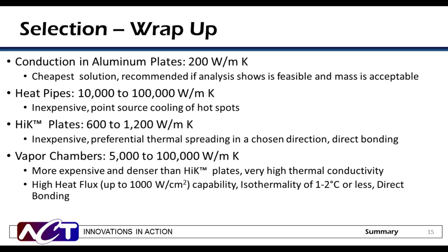Here is a summary of selection criteria across each technology. Aluminum plates have a thermal conductivity of 200 watts per meter K, move heat in two dimensions, and are usually the cheapest solution — use them whenever possible. Heat pipes have a thermal conductivity range of 10,000 to 100,000 watts per meter K and are used for discrete point cooling. High-K plates range from 600 to 1,200 watts per meter K and are used for selected and strategic heat spreading. Vapor chambers range from 5,000 to 100,000 watts per meter K and are higher cost and performance devices, with a condenser surface that is isothermal with only 1 to 2 degree temperature differential across the whole surface.